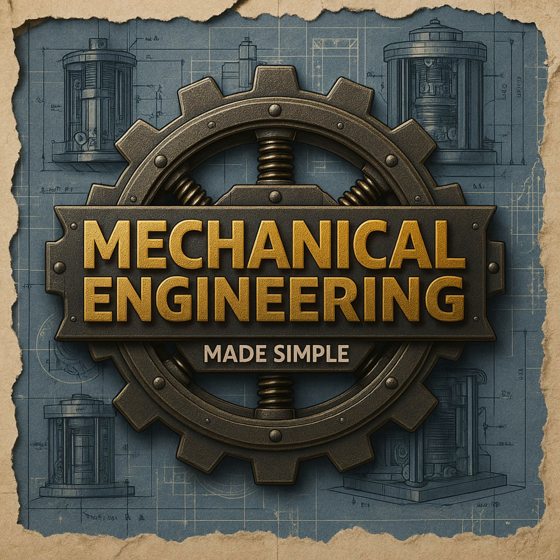There was one specific detail in the text that I found really interesting: spreading resistance. Yes. This is a geometric problem. Imagine you have a tiny chip, say 1 square centimeter, producing 100 watts. You clamp a big heat sink on top of it that is 10 centimeters wide. Okay. You might assume the whole heat sink is working, but the heat has to flow from that tiny contact patch and spread out to fill the base of the big heat sink.